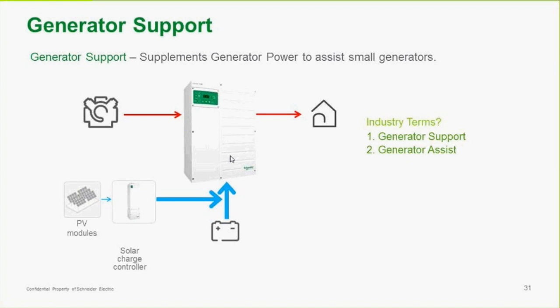In a generator support mode, now we have the generator that's bringing power into the system, and when you have PV production, you're now basically supporting the generator. Or, if the battery's already charged up and you have a large load set that's starting up that the generator may not be big enough to handle, then the PV system will actually support that equipment starting up.